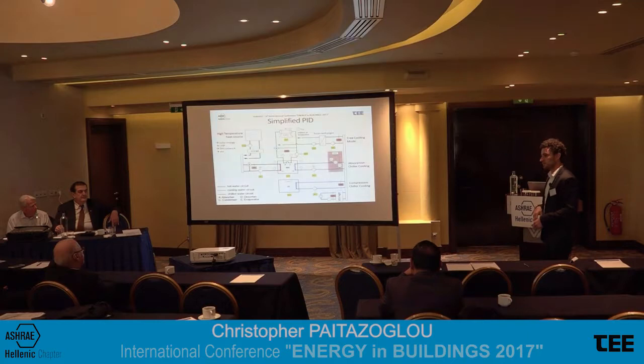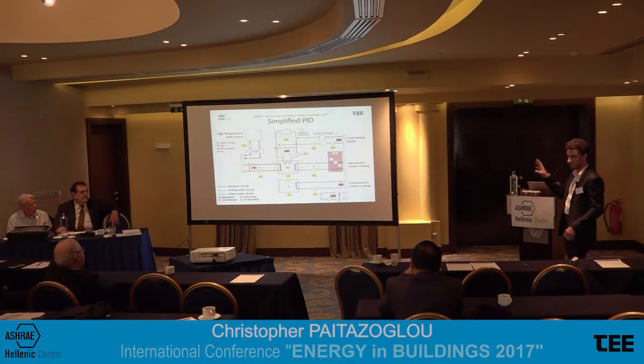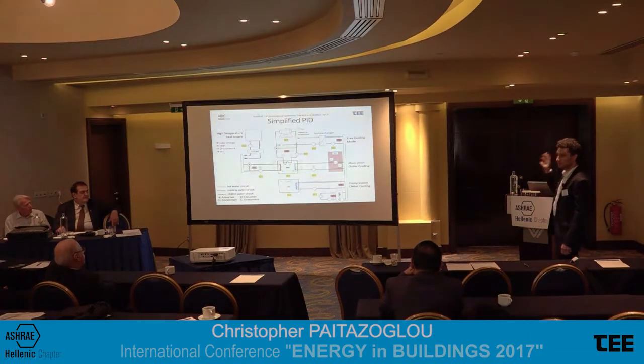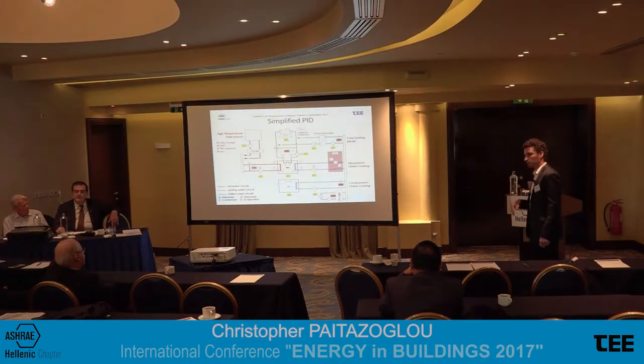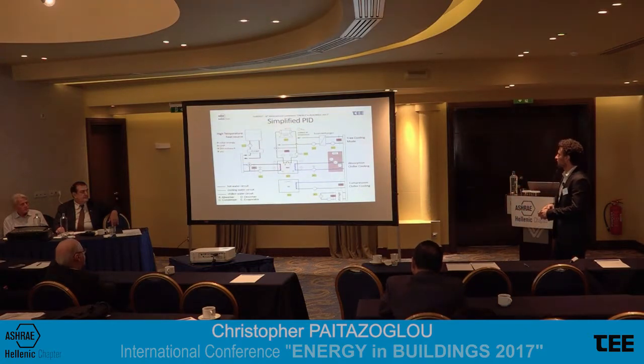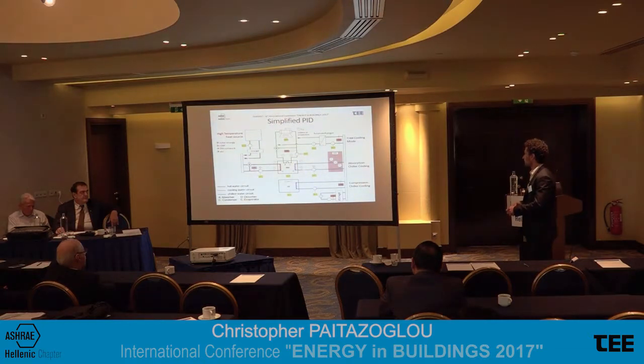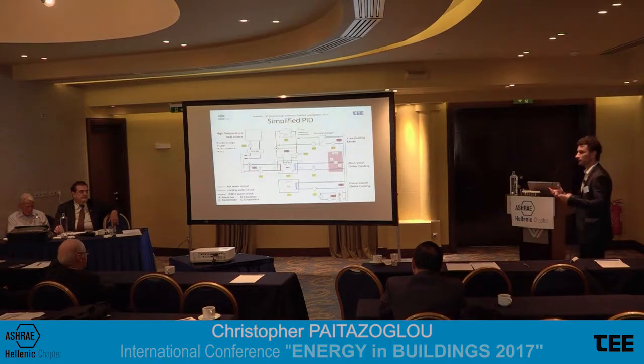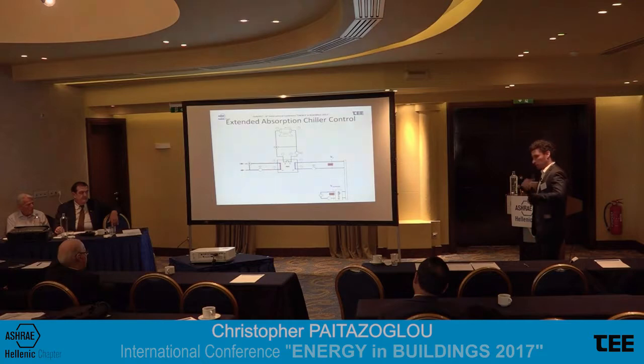So the monitoring of the system, here again you see a very simplified mode, and this is only the sensors that are related to the energy evaluation. There are also other control sensors, etc., that are not shown here. And we see that for all process-related actors and all boundaries, there are heat flow meters consisting of two temperatures on return and supply, a volume flow sensor, a calculating unit, and watt-hour sensors for the electrical components, and all those data is being acquired and is being analyzed. So let's come over to the extension of this absorber control.